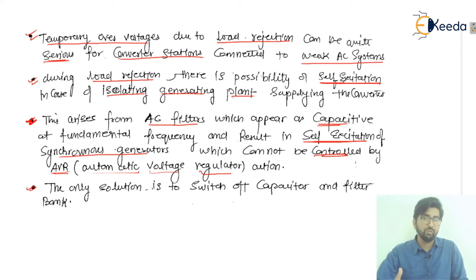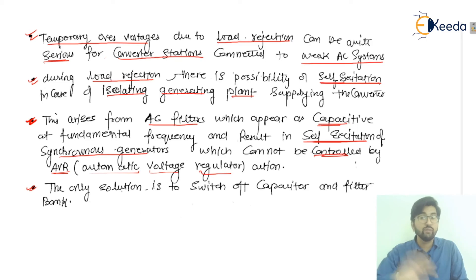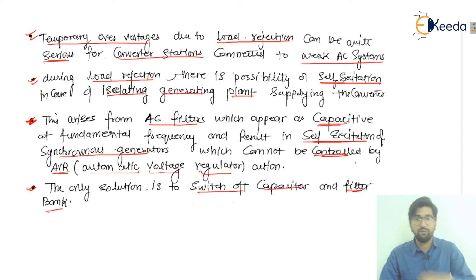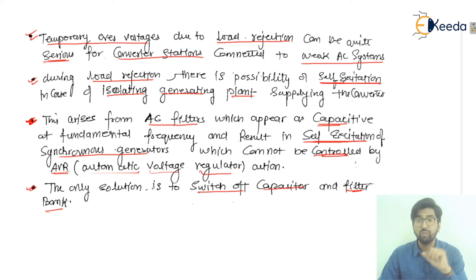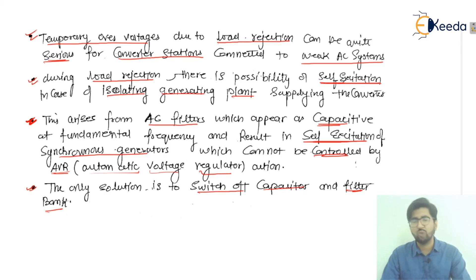Since the automatic voltage regulator is unable to control self-excitation, the only solution left is to switch off the capacitor and filter bank. If the self-excitation process starts to occur and cannot be controlled by the AVR, the only available solution is to switch off the capacitor and the filter bank. I hope you have understood all the points covered. Thank you so much, bye bye.